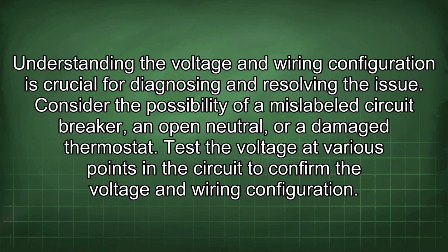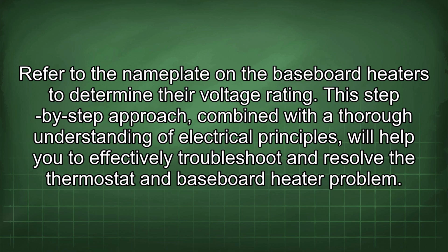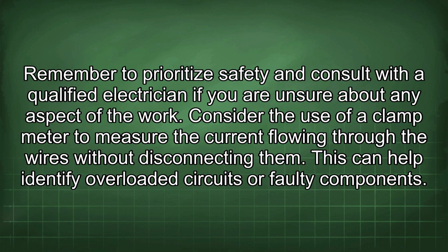Understanding the voltage and wiring configuration is crucial for diagnosing and resolving the issue. Consider the possibility of a mislabeled circuit breaker, an open neutral, or a damaged thermostat. Test the voltage at various points in the circuit to confirm the voltage and wiring configuration. Refer to the nameplate on the baseboard heaters to determine their voltage rating. This step-by-step approach, combined with a thorough understanding of electrical principles, will help you to effectively troubleshoot and resolve the thermostat and baseboard heater problem. Remember to prioritize safety and consult with a qualified electrician if you are unsure about any aspect of the work.